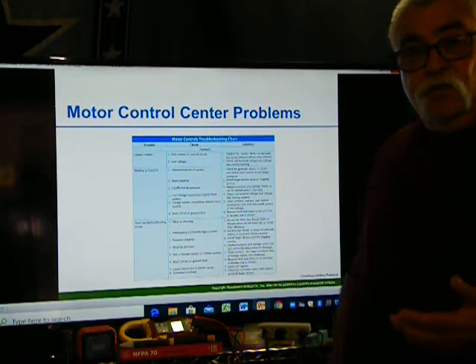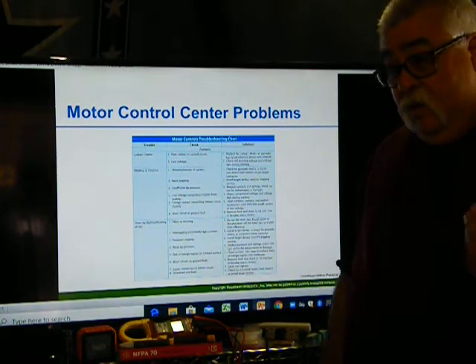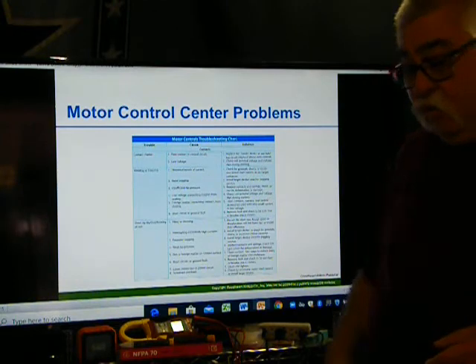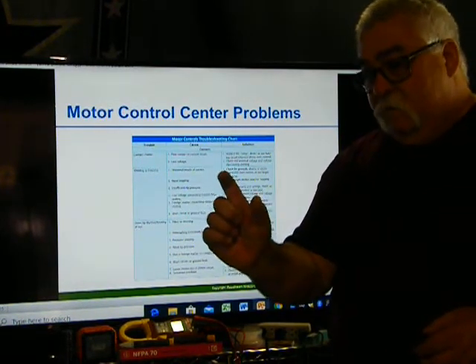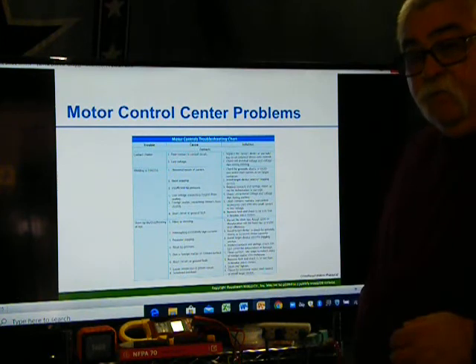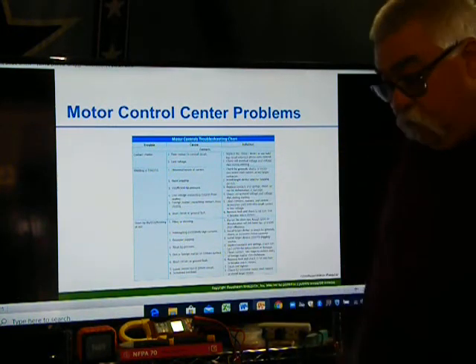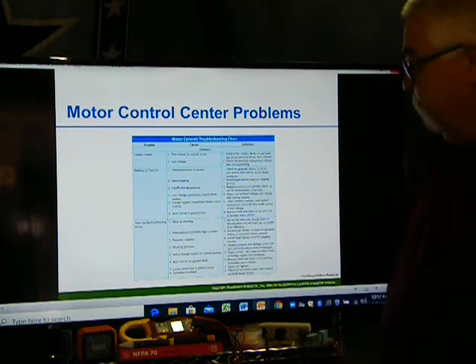Okay, the breaker should have been like a 30 amp breaker, and there was a 70 amp breaker, so they had these number 12s on the 70 amp breaker. You should have seen the wires melted back about 2 inches on all three of them, and the contactor was stuck in the on position, and the breaker didn't trip.